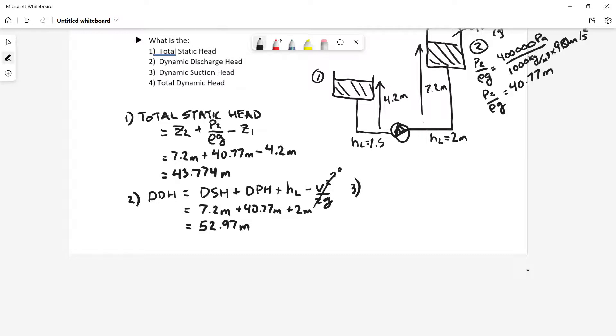My total, or my dynamic suction head, dynamic suction head is going to be equal to my suction static head plus my suction pressure head minus the head loss minus the velocity squared over 2G I'm entering the pump. Okay, my suction velocity head. And once again, that guy is just zero because of my velocities. So my dynamic suction head is going to be 4.2 plus zero. No pressure in that tank. It's open minus 1.5 and I get a value of 2.7 meters.